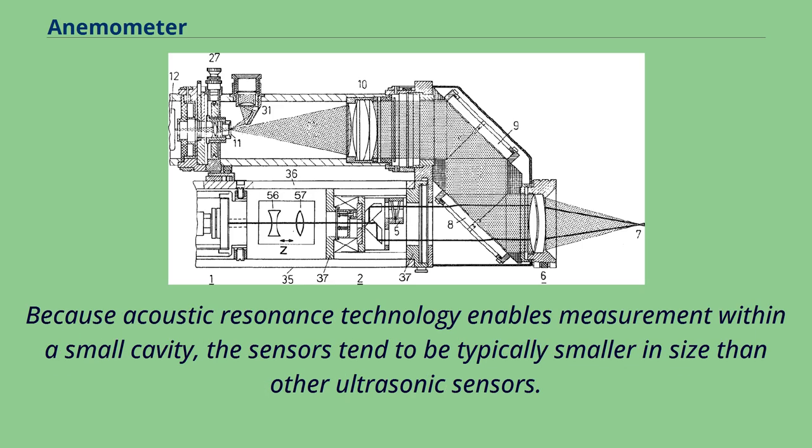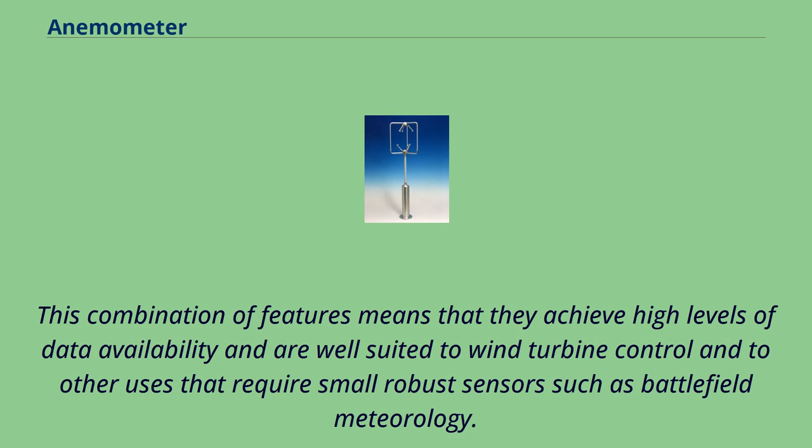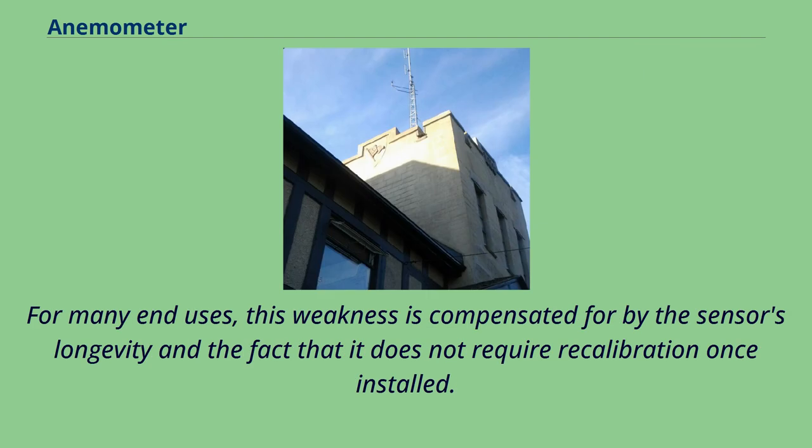Because acoustic resonance technology enables measurement within a small cavity, the sensors tend to be typically smaller in size than other ultrasonic sensors. The small size of acoustic resonance anemometers makes them physically strong and easy to heat, and therefore resistant to icing. This combination of features means that they achieve high levels of data availability and are well suited to wind turbine control and to other uses that require small robust sensors such as battlefield meteorology. One issue with this sensor type is measurement accuracy when compared to a calibrated mechanical sensor. For many end uses, this weakness is compensated for by the sensor's longevity and the fact that it does not require recalibration once installed.